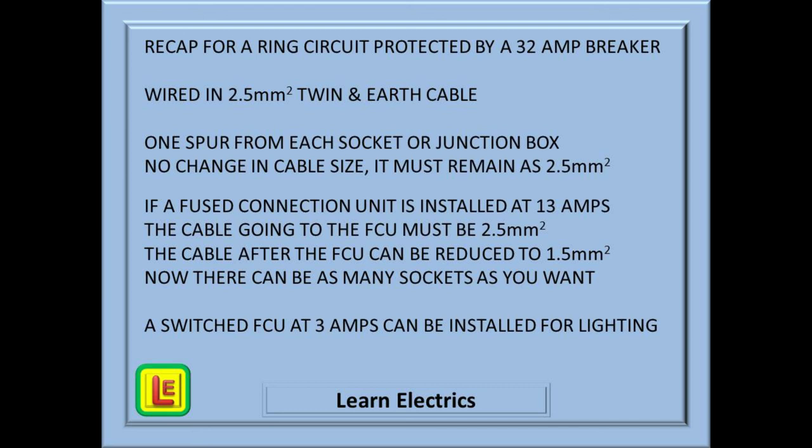A switched FCU can be installed to act as a lighting switch but this must be re-fused at 3 amps or even 1 amp if possible. It must not be left with the 13 amp fuse in it.